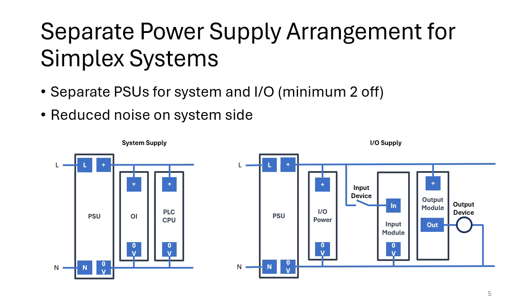One, of course, we get more power without having to go to really big bulky power supplies. You could use 2 5 amp or maybe a 5 amp to 10 amp power supply or so on. Another big reason is it reduces the noise on the system side. Operator interfaces and PLC CPUs are relatively rugged, but if you expose them to too much noise, particularly from output devices which aren't adequately suppressed, you could be running the risk of getting a lot of noise on the system, and that could affect the operation of the operator interface on the PLC CPU. So simply having 2 power supplies like this is a great way of segregating the power and making it quite straightforward and making sure that there's minimal interference across the 2 systems.